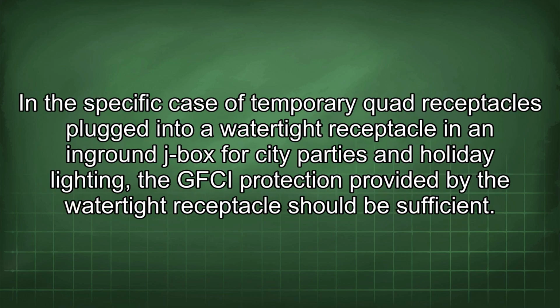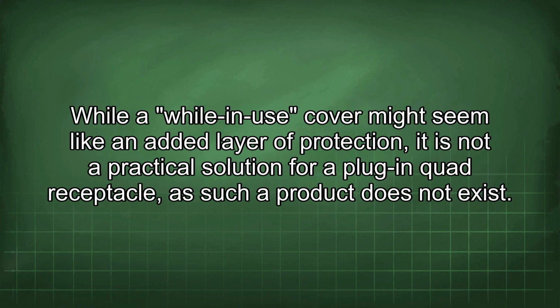In the specific case of temporary quad receptacles plugged into a watertight receptacle in an inground j-box for city parties and holiday lighting, the GFCI protection provided by the watertight receptacle should be sufficient. While a while-in-use cover might seem like an added layer of protection, it is not a practical solution for a plug-in quad receptacle, as such a product does not exist.